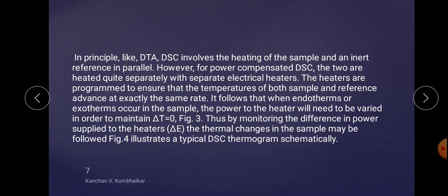It follows that when endotherms or exotherms occur in the sample, the power of the heater will need to be varied in order to maintain delta T equal to 0. For example, which has been shown in figure 3. Now, what is the basic principle of DSC?